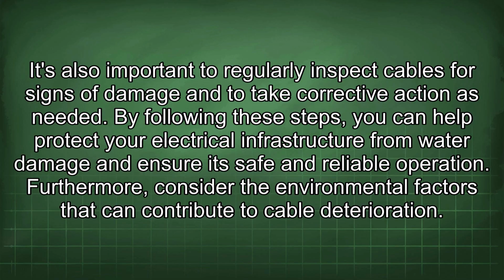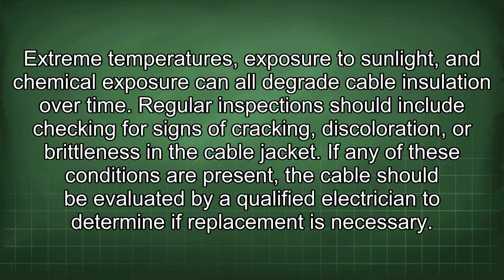By following these steps, you can help protect your electrical infrastructure from water damage and ensure its safe and reliable operation. Furthermore, consider the environmental factors that can contribute to cable deterioration. Extreme temperatures, exposure to sunlight, and chemical exposure can all degrade cable insulation over time. Regular inspection should include checking for signs of cracking, discoloration, or brittleness in the cable jacket. If any of these conditions are present, the cable should be evaluated by a qualified electrician to determine if replacement is necessary.